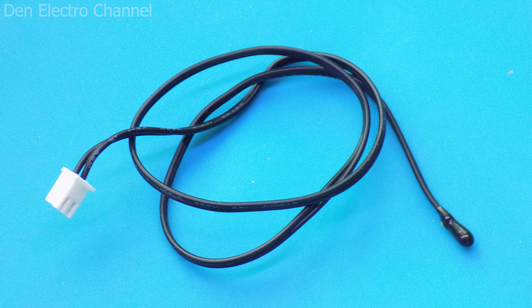As I mentioned earlier, the converter has a built-in temperature sensor and a connector for a remote temperature sensor. The remote sensor isn't included with the converter, but you can buy one separately somewhere. I have just such a one, and it looks like this. In the converter settings, you can configure the protection trip temperature for each temperature sensor.